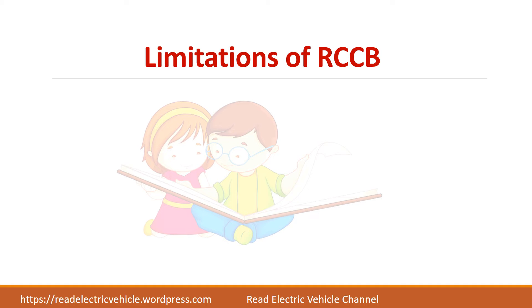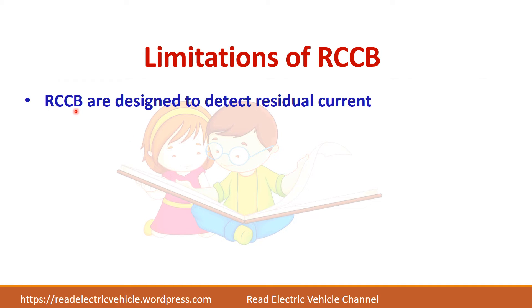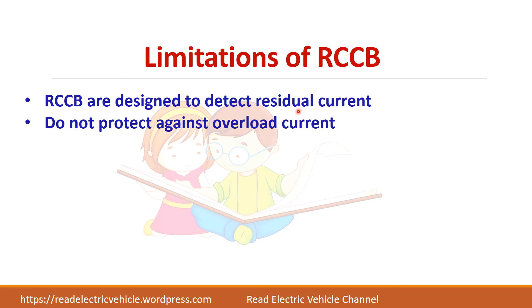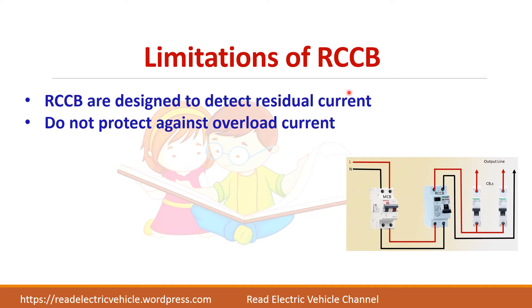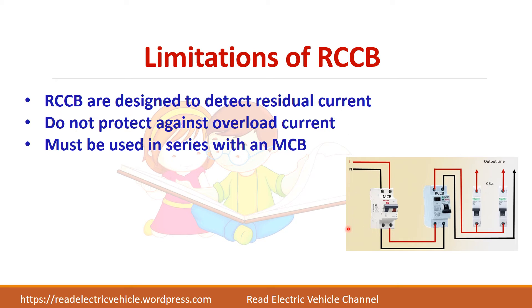The limitations of RCCB: they are designed to detect the residual current and cannot detect overload current. If the current in both lines is the same, the residual current will be zero and the RCCB will not work. It can only detect when there is a residual current. Therefore, it is advised to use an MCB and RCCB connected in series — MCB for overload protection and RCCB for residual current or earth leakage fault protection.